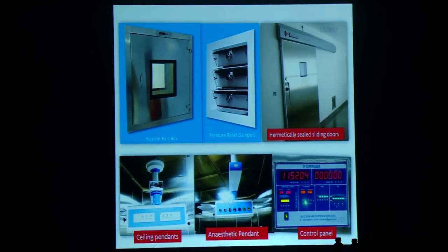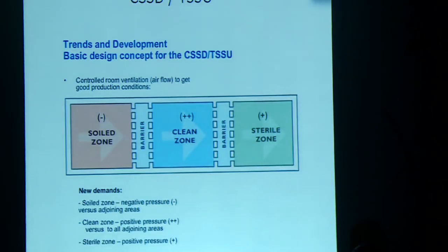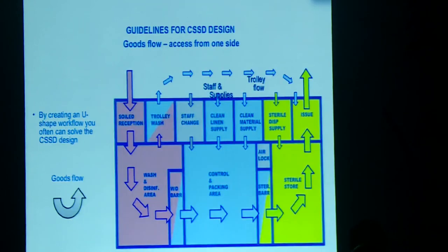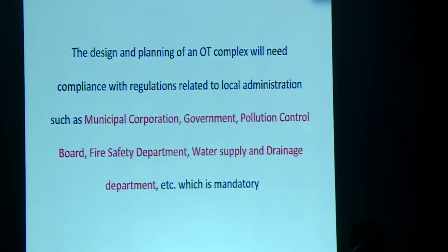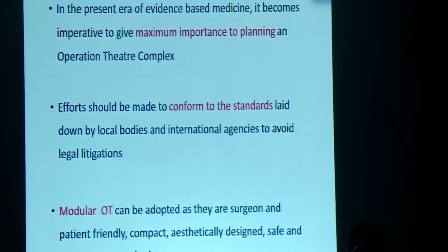The CSSD — Central Sterile Supply Department — is an important part for processing and sterilizing used instruments. It has a soil zone, clean zone, and sterile zone with differential air pressure. The flow goes from soil reception to the control and packing area, then to the sterile area, and finally to the supply part. The design and planning of an OT complex must comply with regulations relating to local administrations such as municipal corporation, government pollution control board, fire safety department, and water supply and drainage department. All these certifications must be obtained to have a well-planned OT.